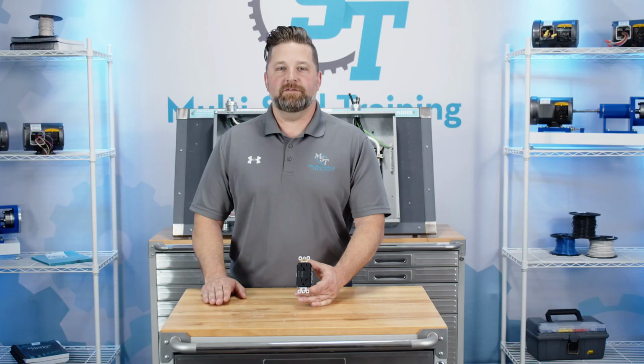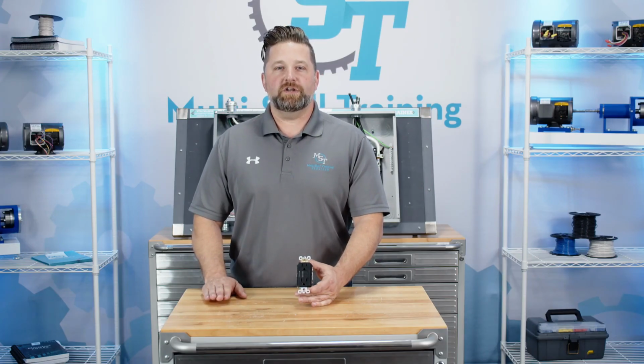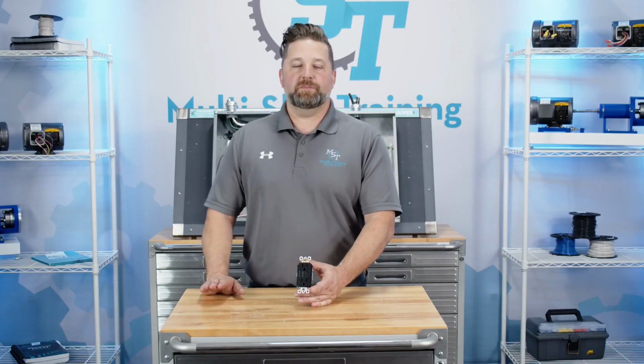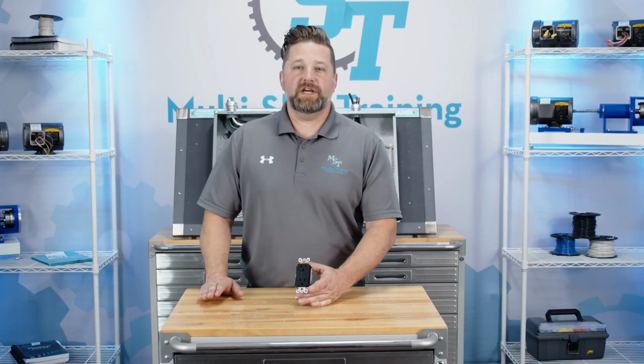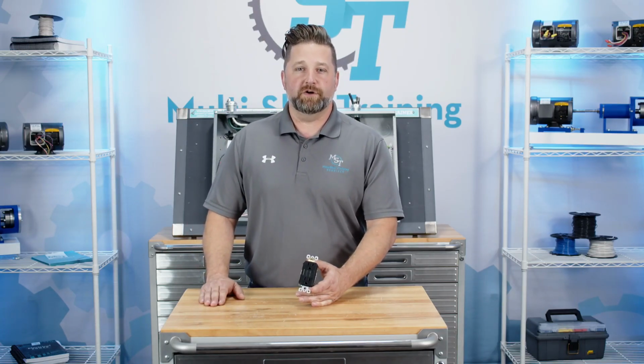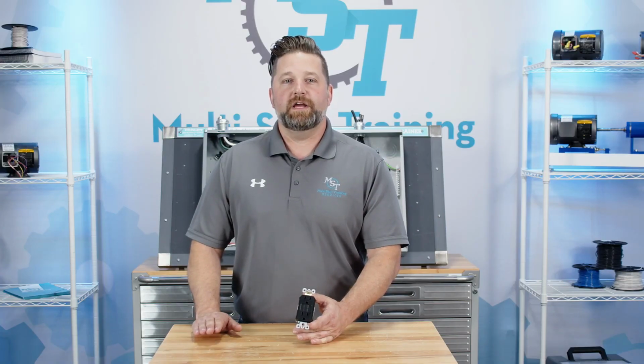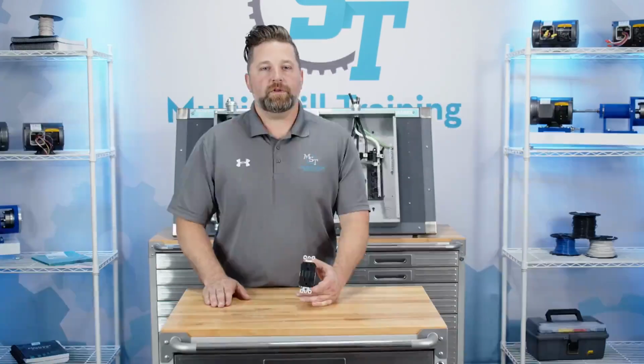If it detects even a very small ground fault, a condition where electrical current is leaking to ground through an unintended path, such as a person or water, the GFCI quickly shuts off power to the circuit. This fast action helps prevent serious injury or death from electric shock. Any current flow above a safe level is considered a ground fault and triggers the GFCI to trip.